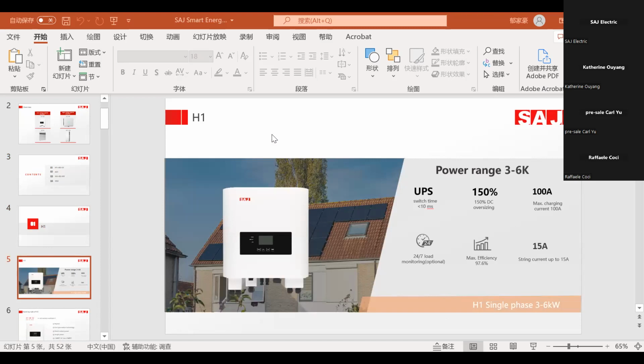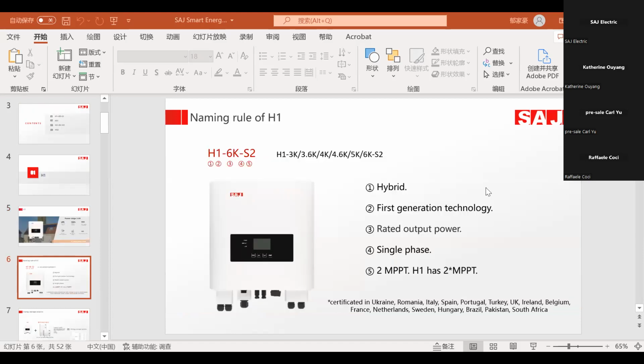Firstly is our H1 hybrid inverter. It has only single phase, and the power range varies from 3 to 6 kilowatts. Because it is connected with the batteries, it has the UPS function, and it also has 150% DC oversizing. The maximal charging and discharging current is 100 ampere. It is related to the maximal charging and discharging current of the B2 low voltage batteries. And we have the string current up to 15 ampere. The naming rule: the H means hybrid, and it has 3K, 3.6K, 4K, 4.6, 5, 6, and it has two MPP trackers.